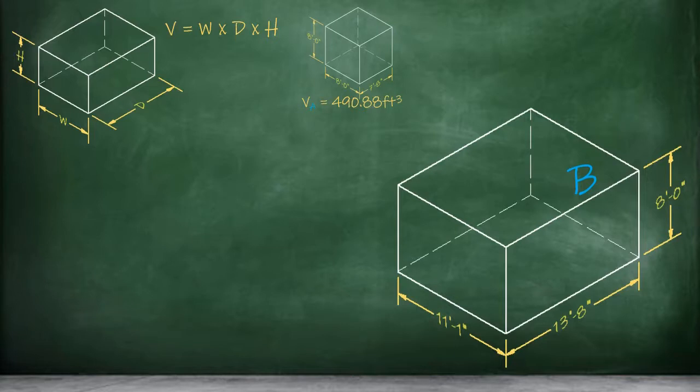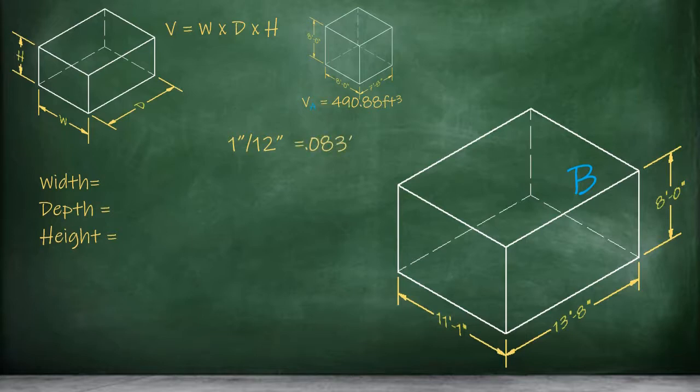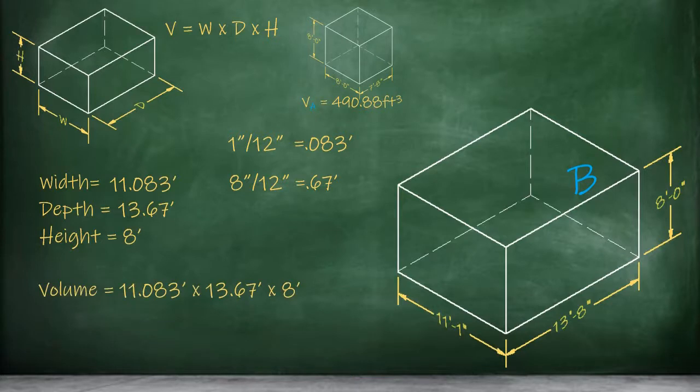Next we'll look at part B. Again, we're going to use the width, depth, and height dimensions. Our width dimension is 11 feet 1 inch, so we need to convert the 1 inch portion into decimal feet by dividing 1 by 12, which equals 0.083 feet. When we add this back together with our 11 whole feet, we get a width dimension of 11.083 feet. Our depth dimension is 13 feet 8 inches, so once again we'll need to convert this into decimal feet. 8 inches divided by 12 inches equals 0.67 feet. When we add this back together with the whole feet, we get a depth dimension of 13.67 feet. And our height dimension is still 8 feet exactly, so no need to convert anything there. 11.083 feet times 13.67 feet times 8 feet equals a volume of 1212.04 cubic feet for part B of our space.